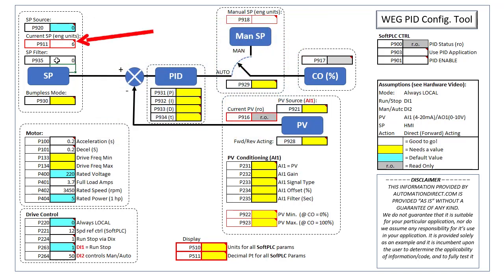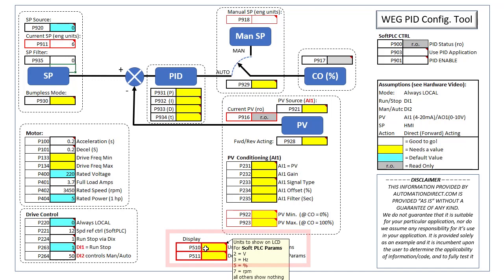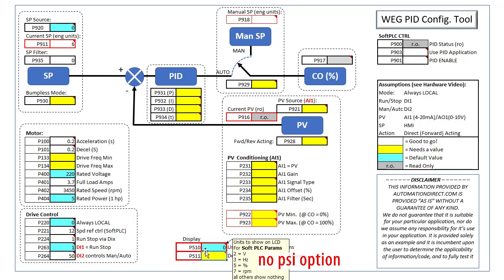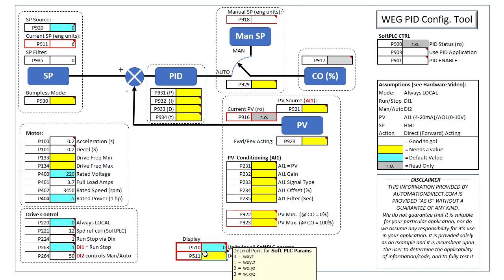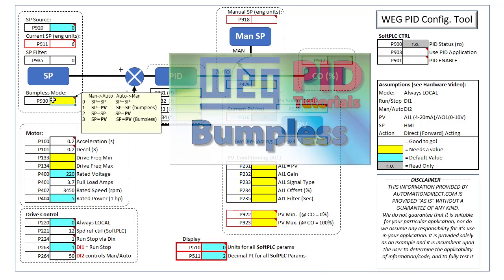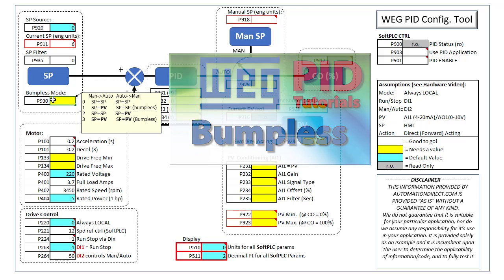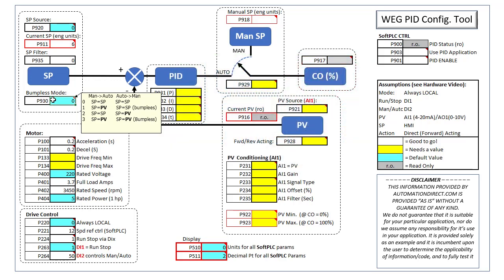The red box reminds us that this is entered in engineering units, which means we need to configure the display for engineering units. Parameter 510 sets the units indicator in the HMI display. There is no indicator for PSI, so we'll set that to a zero to display nothing. Parameter 511 sets the decimal point for all soft PLC parameters that use engineering units, so let's make sure that's two decimal places. Finally, we want to disable bumpless mode while we are getting things set up, so we'll put a zero here.